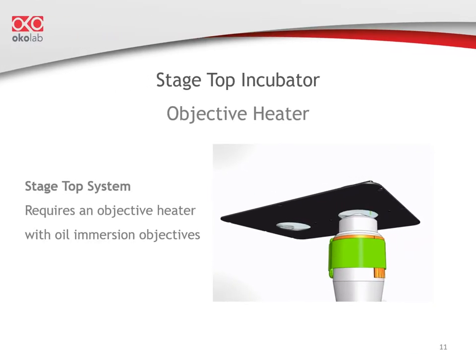When imaging with an oil immersion objective, we recommend using an objective heater — represented here by a heating band in yellow, secured around the objective by a green strap. An oil immersion objective will touch the bottom of the well through the oil and will draw heat away from your sample. This is why an objective heater is recommended.